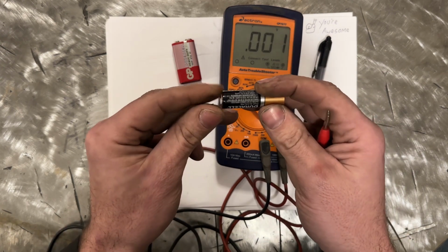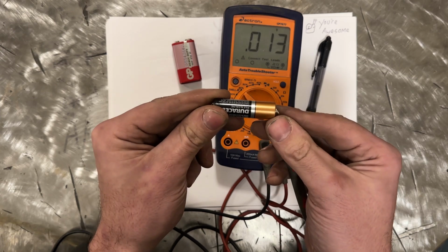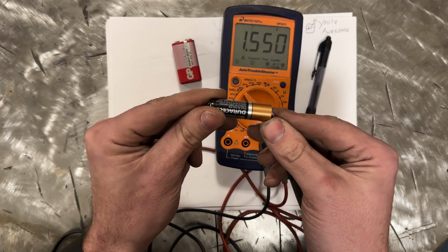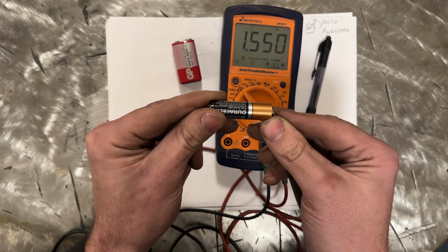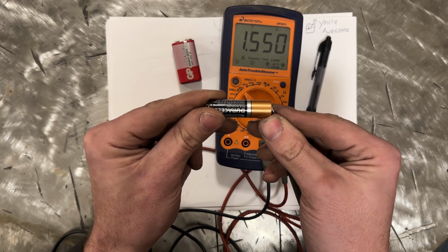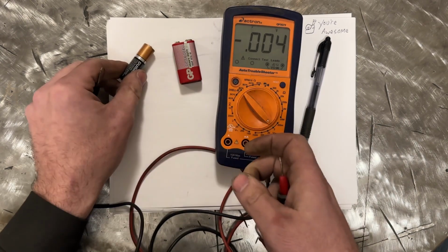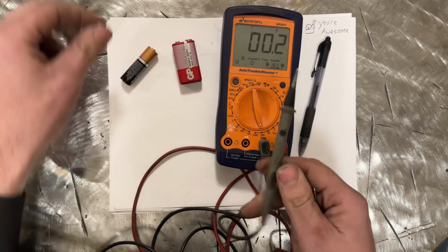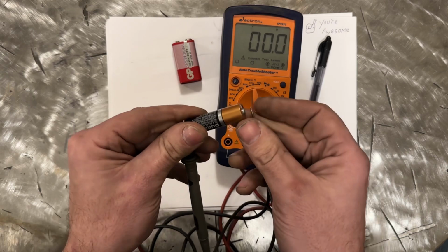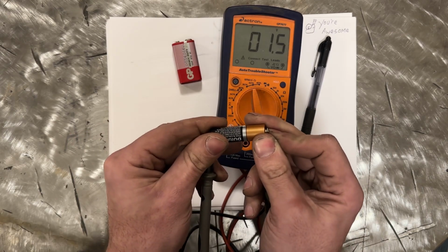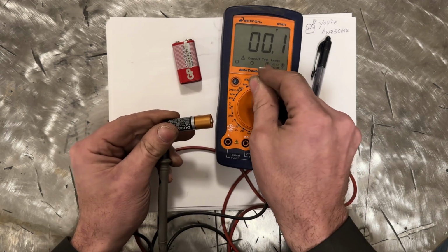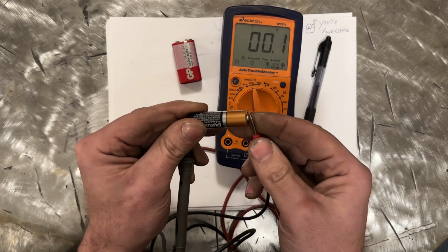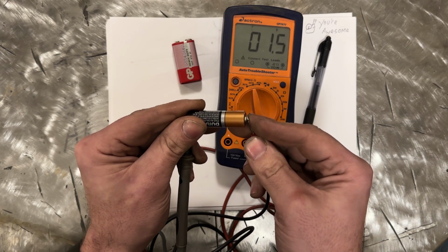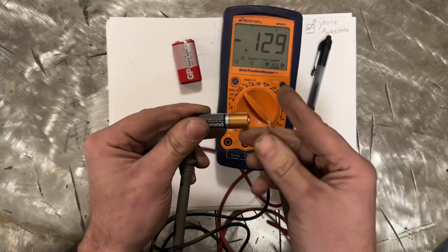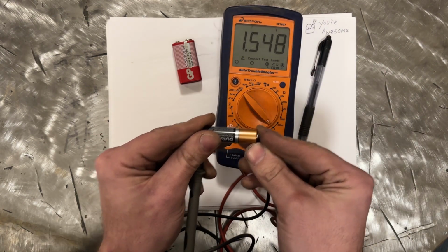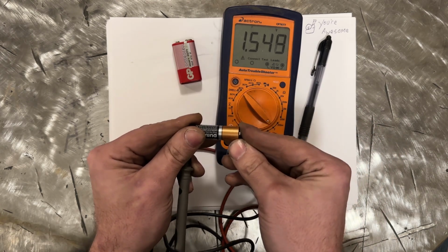Now, I'm not sure what this battery will read fully discharged, because it will never read, say, 0. Even with a full discharge where it won't run what you hooked it up to, it still will read some voltage, generally speaking. Now, I'm going to move this up to 200 volts, and we're going to check the same thing again, and you're going to see on the meter it just reads 1.5. What it ends up doing is moving the decimal point over, and then it cuts off. So on this scale, yeah, it's 1.5 volts, but on the 2 volt, we have more information. So rather than just 1.5, it's 1.548.